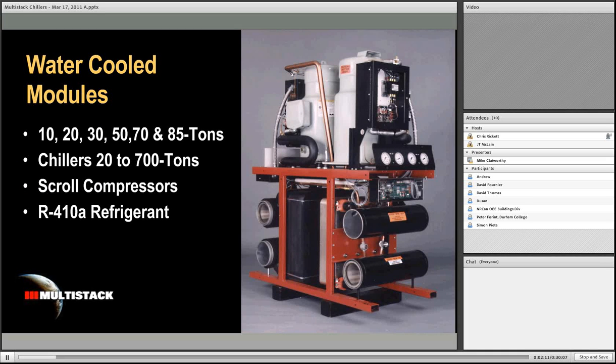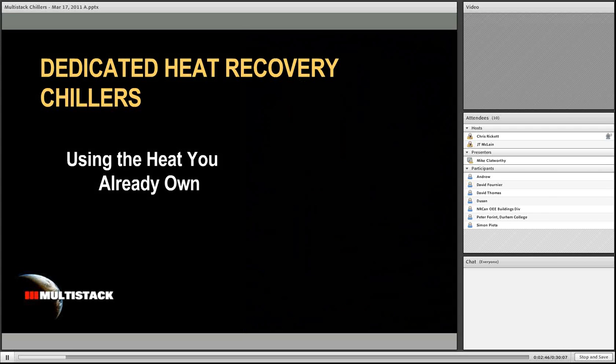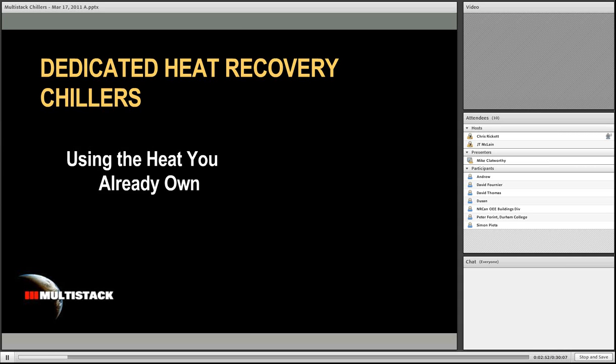We test extensively to make sure that the efficiency and capacity that we promise is what we deliver. So basically, Multistack started by providing modules of chiller capacity. Here in front of us we see a 30-ton module. Modules are available from 10 to 105 tons and potentially larger than that later this year. But we can use them to assemble a chiller of several hundred tons. Specifically, the equipment that we're talking about today has scroll compressors with R410 refrigerant. And if we need to do very high temperature water, we'd be talking about R134A. But this is a typical module. This is what we would be using in our heat recovery applications and our heat pump applications.